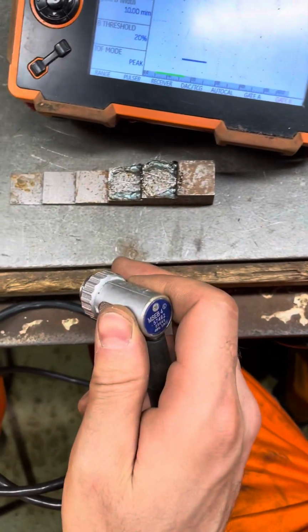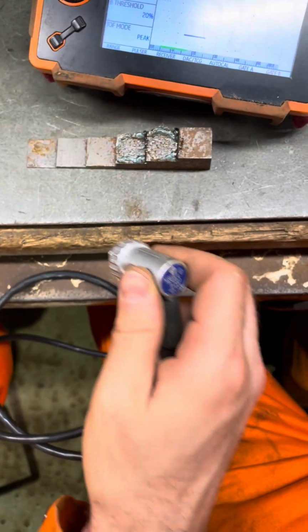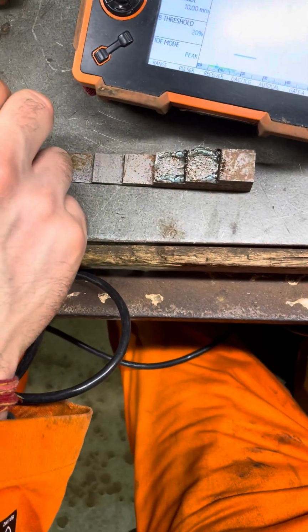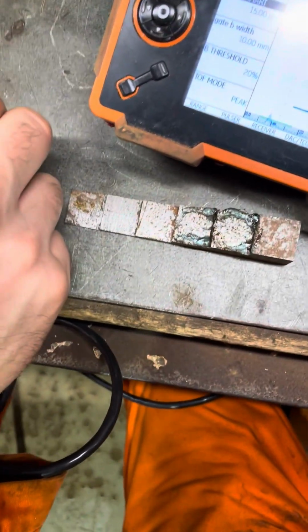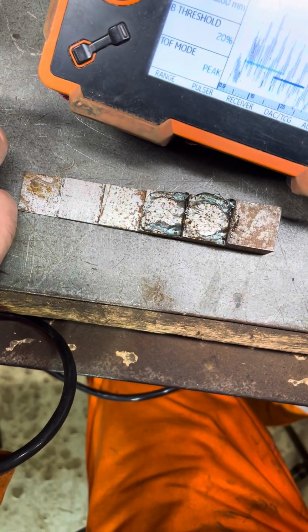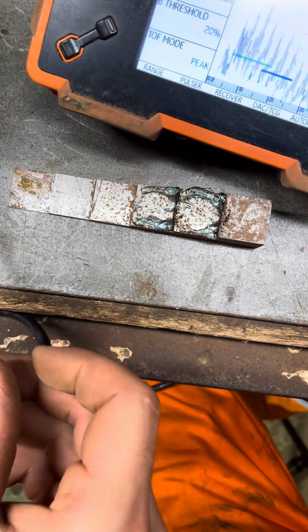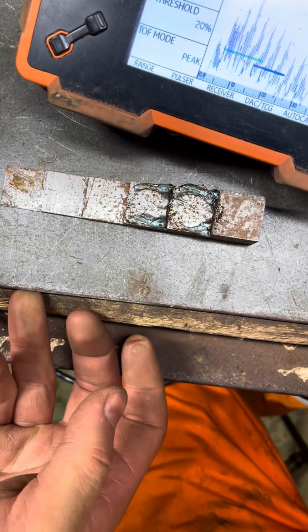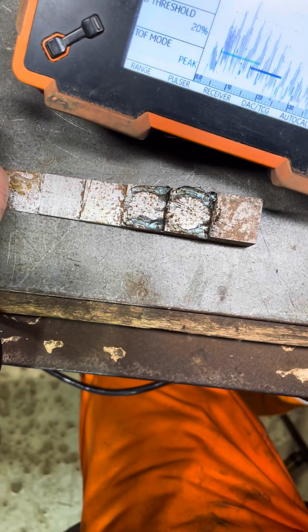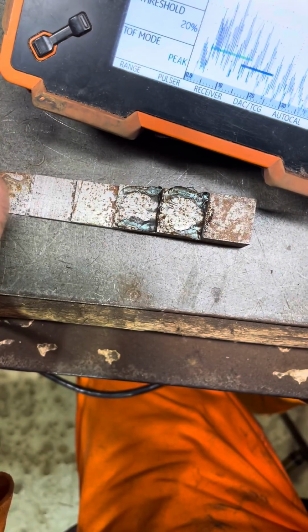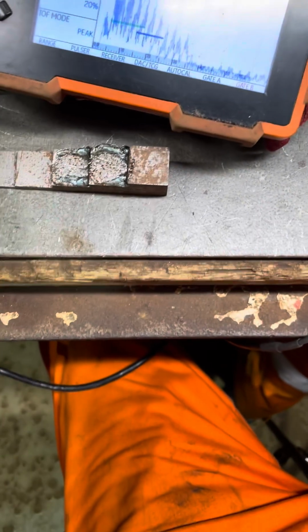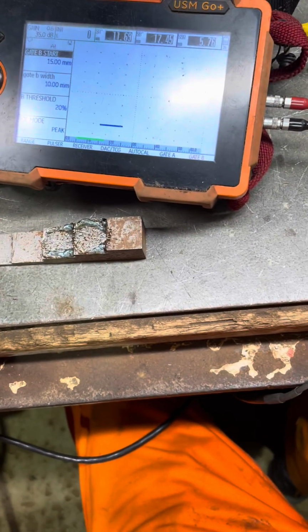Let's say we don't know the thickness of the metal, so we take a measurement on the metal. But this is a different metal. Yes, but we can certainly check, we can look at it right now and see precisely what it shows us. It gives a very poor reading because it's about 3 millimeters thick. We won't be able to measure it because this probe won't work. This probe gives completely nonsense readings. You can see that, right? No. It doesn't matter that it's galvanized.